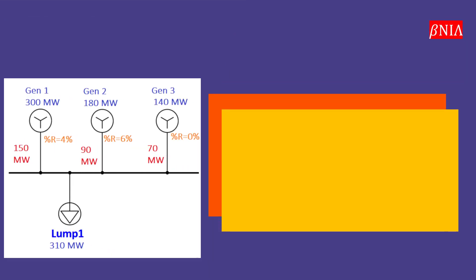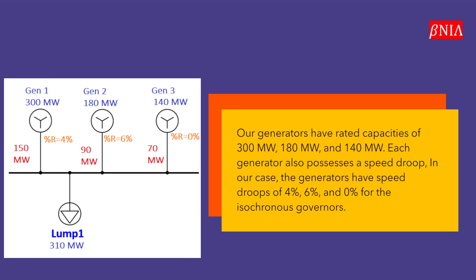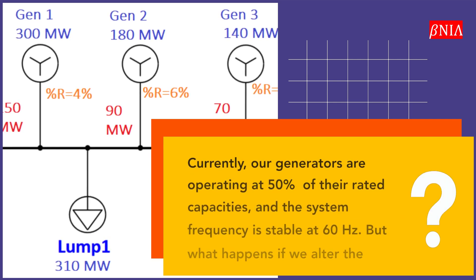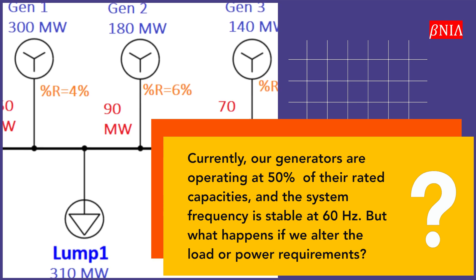Our generators have rated capacities of 300 MW, 180 MW, and 140 MW. Each generator also possesses a speed droop — in our case, the generators have speed droop settings of 4%, 6%, and 0% for the isochronous governor. Currently, our generators are operating at 50% of their rated capacities, and the system frequency is stable at 60 Hz.